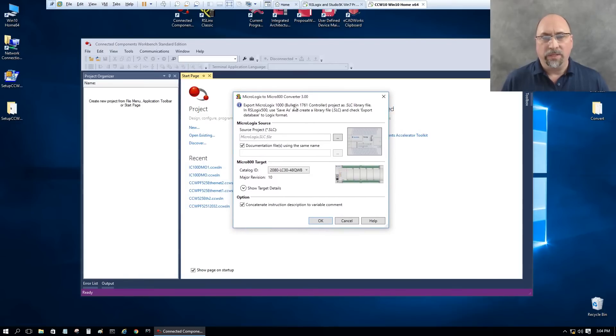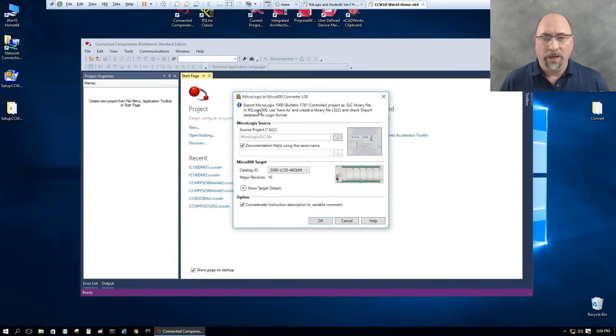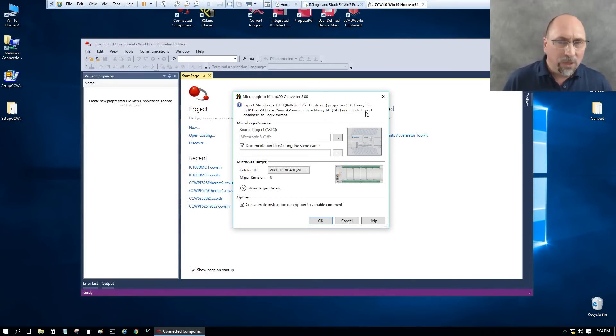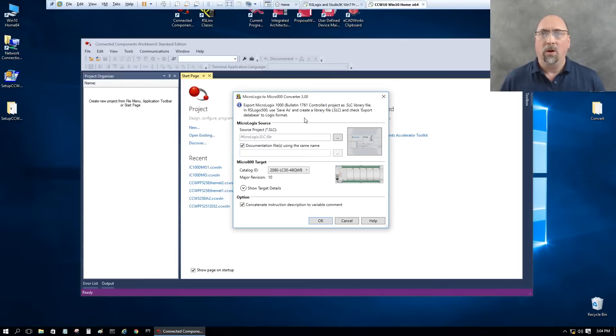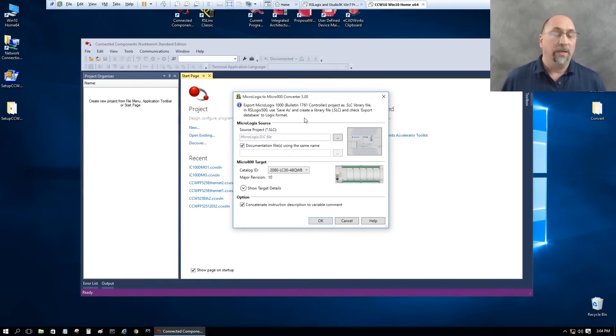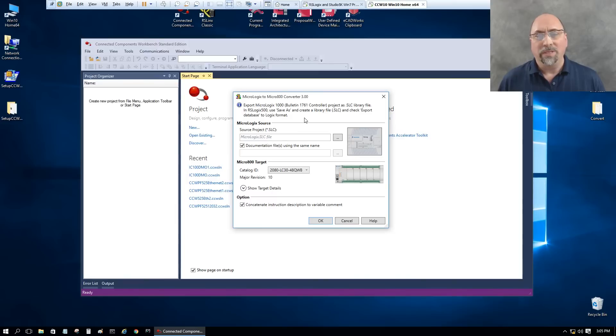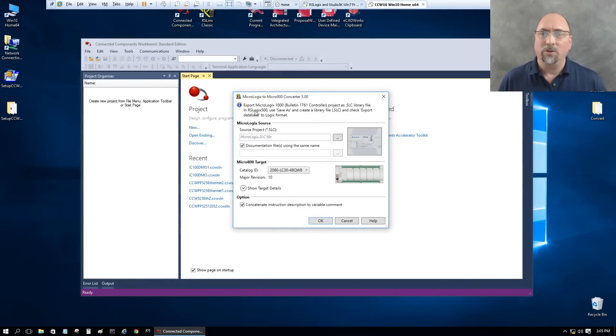Okay, here it's telling me I need to export my MicroLogix 1000 project as a .slc library file in RSLogix 500 and use the Save As to create a library file while checking the export database to Logix format. I can do that. Now I want to make it clear though, I tried to do this in RSLogix Starter Lite and the licensed copy of RSLogix Starter, and neither of them can do this. The reason is they don't have the ability to do the SLC library export. So you can see that's why they're saying use RSLogix 500 here.